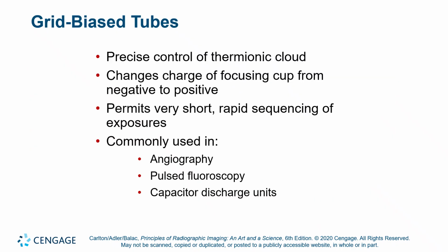All right, now this is the latest and greatest. This has come out since I've been an X-ray tech. And it really only made sense to add this once we got to digital image receptors. So this is called a grid bias tube. What you can do with that focusing cup is alternate positive and negative charge through it. Okay? And so you still have a space charge at the bottom of the bathtub. When the focusing cup is negative, it's raining that charge in, but when you flip it to positive, it actually grounds out the filament current.